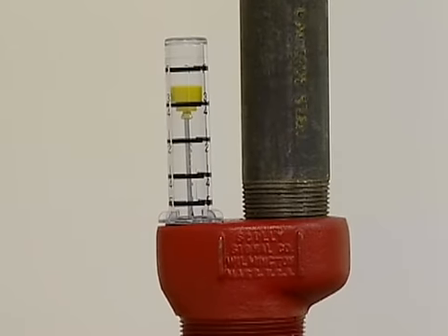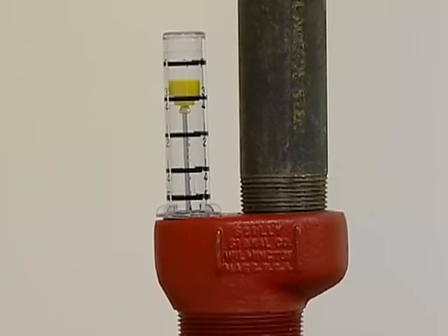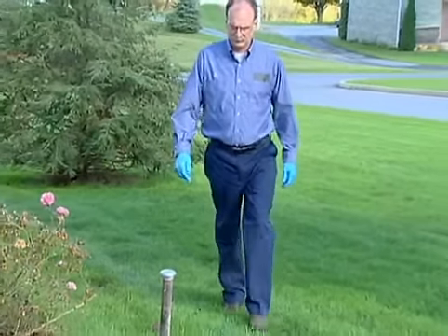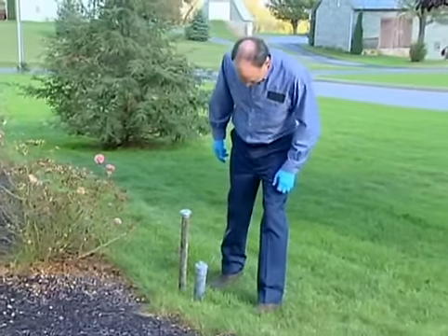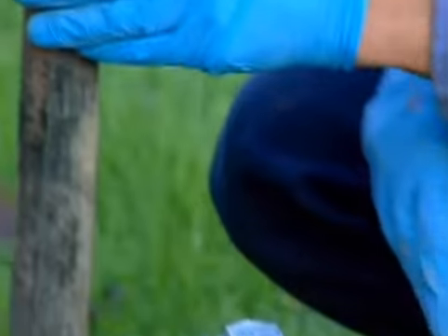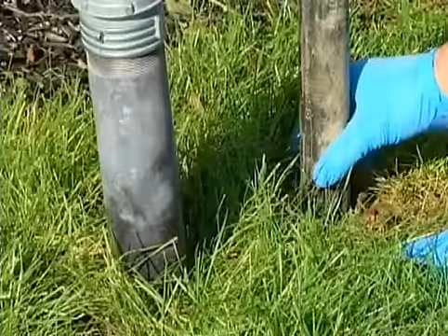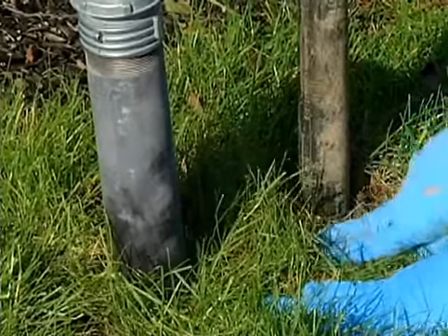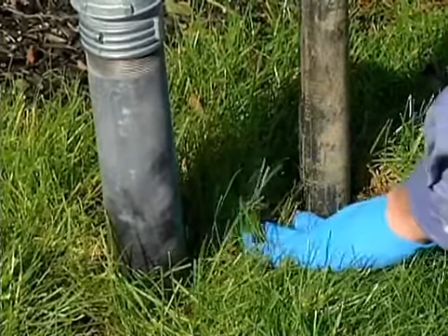Inspect the oil tank for visible leaks and note the level on the gauge. Check the fill and vent pipes. Make sure that the caps are in good shape, fit properly, and are not obstructed. Check the condition of the pipes. Rotted pipes can allow water to enter the tank.